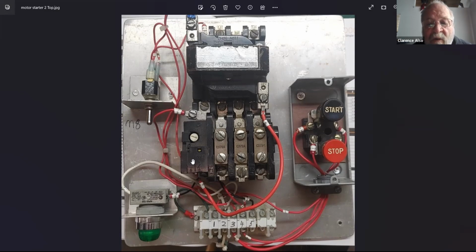The bottom number was there, T1, T2, T3, and that goes out to your motor. If you follow that up through the heater, it goes to some screws above the overloads. This is where your 480 comes in. That 480 flows through the heater down below, and that heats it up to a certain spot. If you're drawing too much current, it gets too hot, and those heaters will pop that thermostat. We'll show you where the contacts are for that thermostat in the next picture.